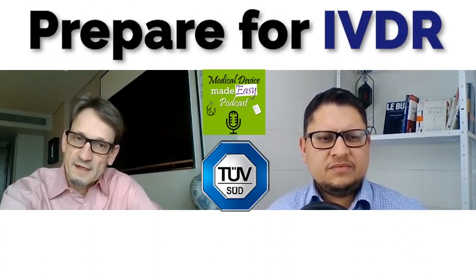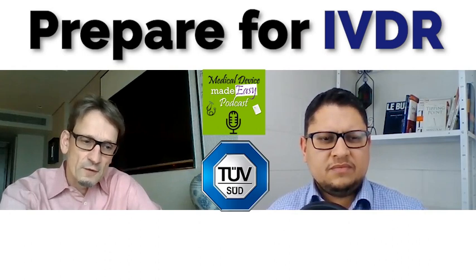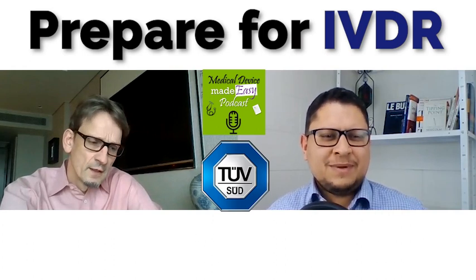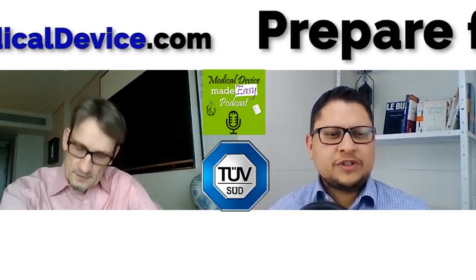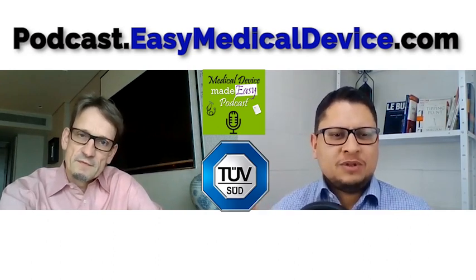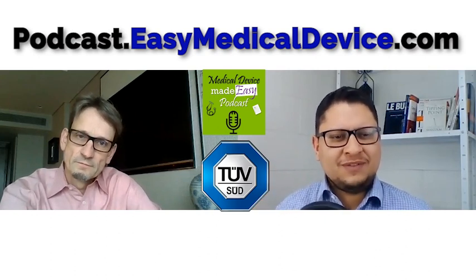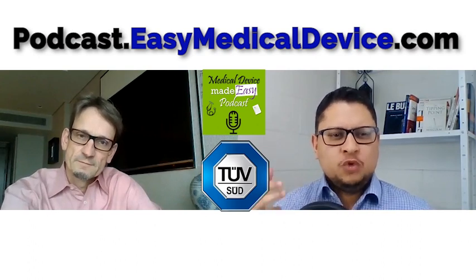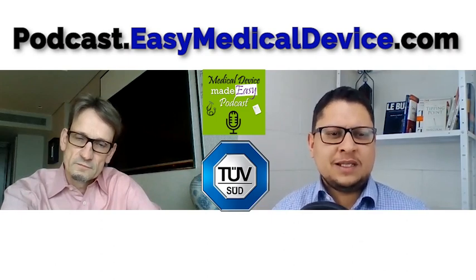Another difference is that the scope, so the definition of what falls under this regulation, is increased. We have, of course, technological development has proceeded. We have a lot of new types of devices like software devices. We have devices provided through the Internet. All these things fall under the regulation as well. So it's the same as the MDR. The MDR also included more devices or more scope because of new technologies, new items that come on the market, and maybe also history where they see that some topics, some devices were not included. So the same for IVDR. Exactly. So maybe they are looking at what happened on the market or history, and they say this should be now included inside the regulation.